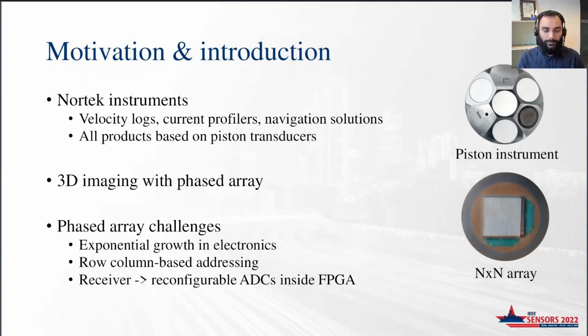The instrument transmits acoustic waves. These waves are reflected back to the instrument by the suspended particles inside the water, and our instruments measure the shift in Doppler frequency, and from that shift, speed or velocity is calculated. All of our currently available instruments are based on piston transducers. We can see an example piston instrument in this slide as well.